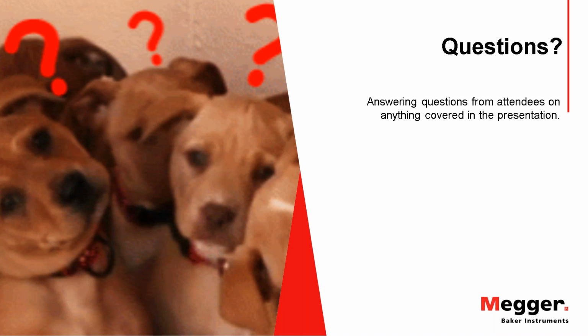Okay, the next question is, what is the accepted voltage for surge testing? There's a couple of standards that we use for surge testing. The IEEE standard, which is IEEE 522, gives us a formula, which I don't have handy on the slide to show you, but basically it uses the per unit values. Per unit is a way of getting the equivalent DC stress per phase. So for a 460 volt motor, we divide that by the square root of 3, multiply by the square root of 2, and that gives us the 1 per unit, and then we multiply that by 3. It's actually like 3.1, something like that. They multiply by that, and that gives you your test voltage.